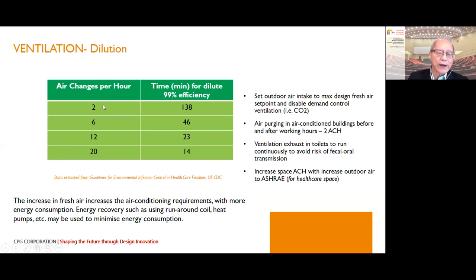2 air changes is recommended for normal buildings. For isolation rooms, we typically use 12 air changes, and for more critical, more dangerous viruses, 20 air changes.